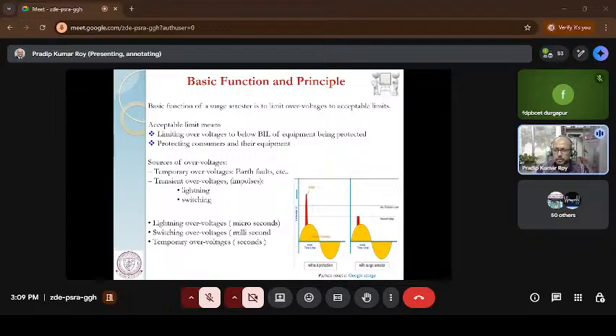For temporary overvoltage we mostly use an electronics surge arrestor, but for transient overvoltage we use an electrical or high voltage surge arrestor. When I talk about this high overvoltage, it is basically a spike, an impulse kind of thing. It has a rise, and at the same time it has a fall also.